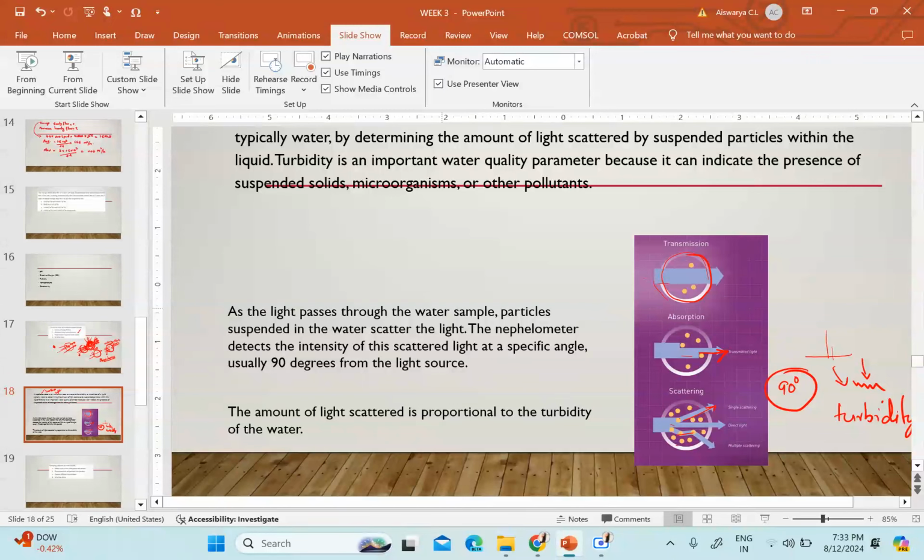Like that, in the nephelometer the turbidity range is between 0 and 40. I think that is the maximum range possible in the machine. When I checked it was like that. I can check again, but I don't know how to convert it.